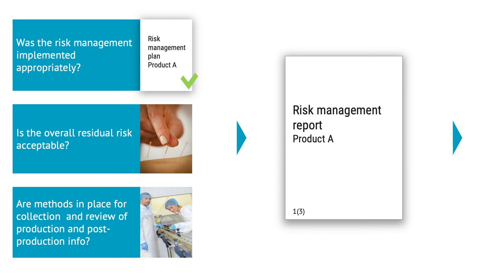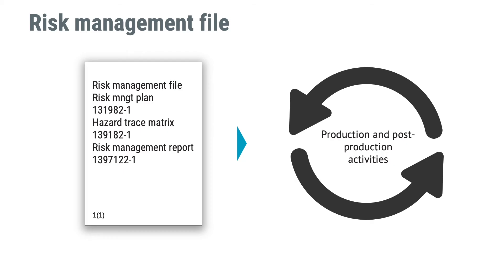The results of your risk management review should go into the risk management report. At the end of your development project you should also establish a risk management file, which is a set of records and documents that are outputs from your risk management process. A practical way to define what is part of the risk management file is to create an index pointing to all relevant documents and records. Thereafter you should continue with production and post-production activities — sometimes you will learn frightening things like risks you did not identify, and sometimes good things, like that certain risks don't occur as often as you thought. Production and post-production activities are about closing the loop to make risk management a continuous life cycle process, keeping the risk management file accurate and up-to-date.